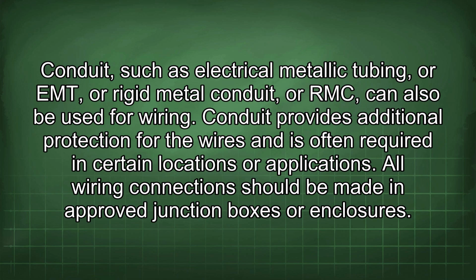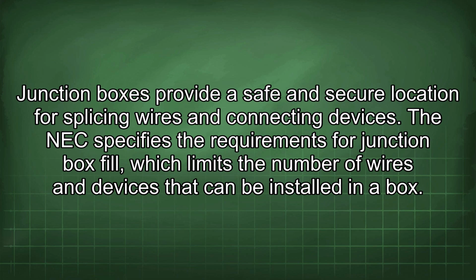Conduit such as electrical metallic tubing, or EMT, or rigid metal conduit, or RMC, can also be used for wiring. Conduit provides additional protection for the wires and is often required in certain locations or applications. All wiring connections should be made in approved junction boxes or enclosures. Junction boxes provide a safe and secure location for splicing wires and connecting devices.